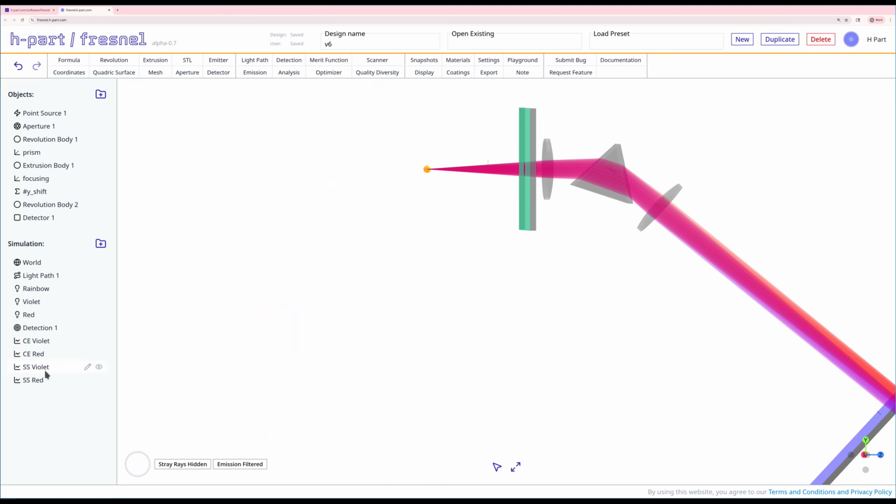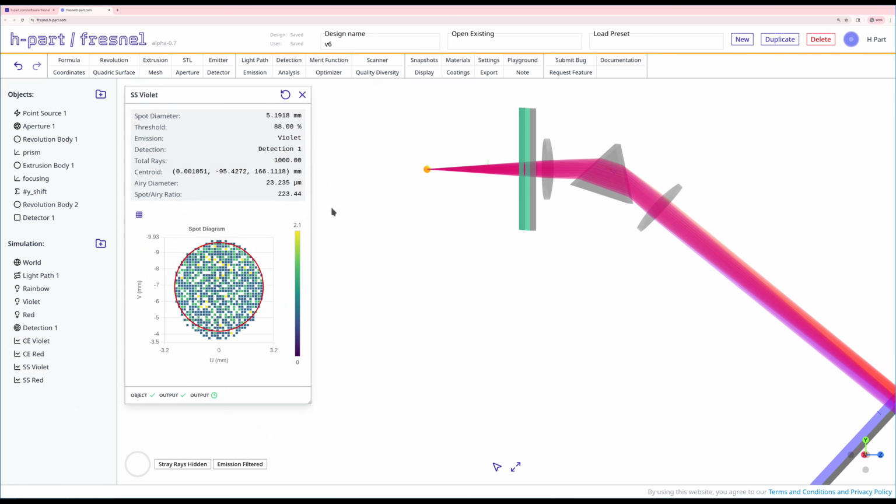And of course we can take a look at the spot size, which is going to be less good. We have this giant 5mm spot, and it's got this kind of smear to it. We really don't want that. We need to get the spot size down into the, hopefully tens, but potentially hundreds of microns so that it spreads over a few pixels. Ideally, when you're designing a spectrometer, you want to design your spot size based on your pixels so that it straddles, say, 1.5 or 2 pixels. If you match it to a pixel, you can sometimes get aliasing effects.